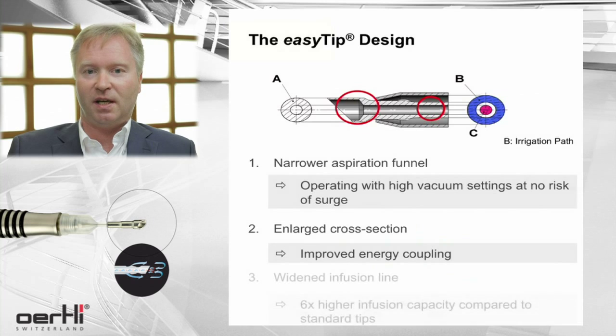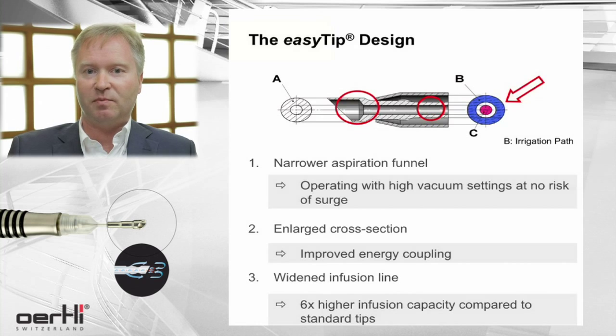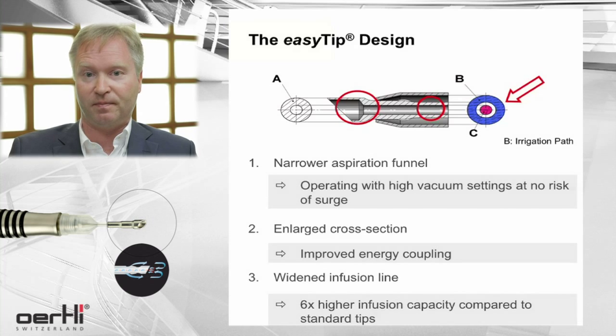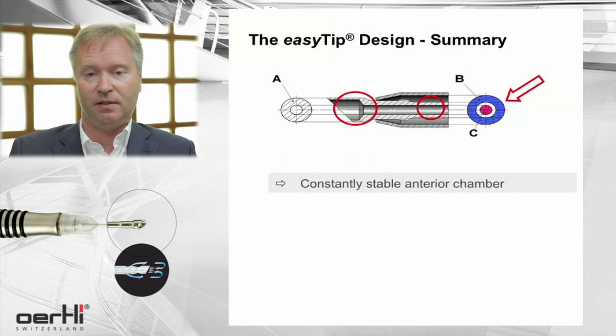The third change is related to the infusion line. Given that the aspiration funnel has been made narrower, there is more space now for the infusion line, giving you a high infusion capacity which is around six-fold higher than compared to standard conventional tips. So you are achieving a constantly stable anterior chamber.